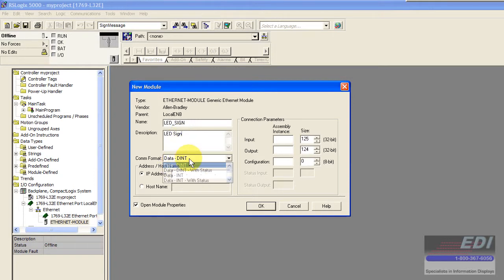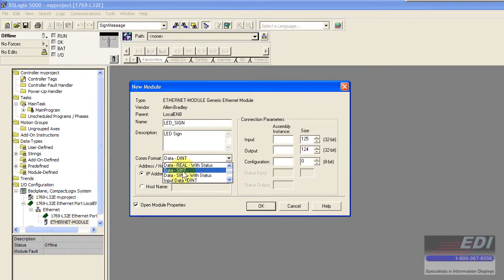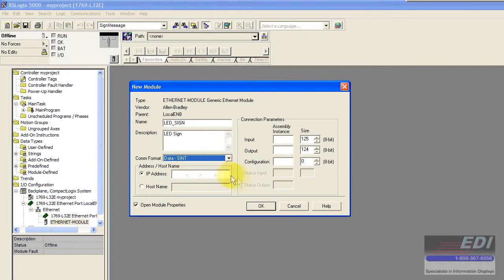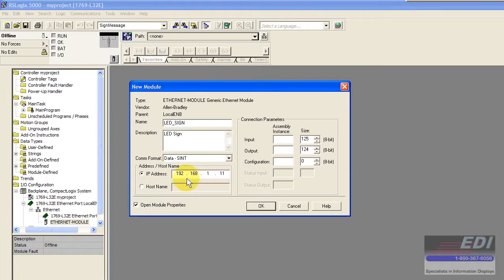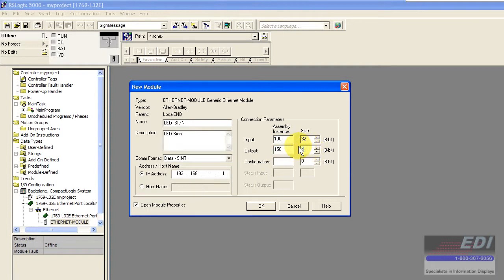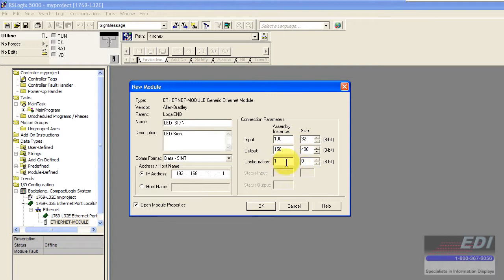As far as com format, this is very important. We want to select data single integer registers. That's the com format we configured when we downloaded that CFG file earlier. Then it's important to put the IP address of the actual communicator device. In this case it's 192.168.1.11. Our input is assembly instance 100 and we're exchanging 32 bytes of input. Assembly instance 150 and we're exchanging the full 496 bytes output with one assembly instance but we're not actually going to send any bytes that way.